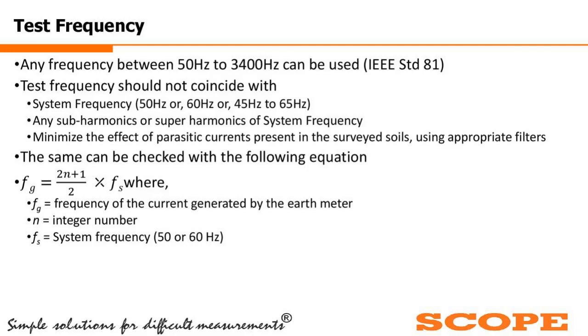However, they have also said the test frequency should not coincide with the system frequency, which is 50 hertz or 60 hertz, being a universal system frequency across the globe. We can say it should not be within 45 hertz to 65 hertz, considering the frequency fluctuation bands. And the test frequency should not be any subharmonic or superharmonic of the system frequency, to minimize the effect of parasitic current present in the surveyed soil, using appropriate filters.